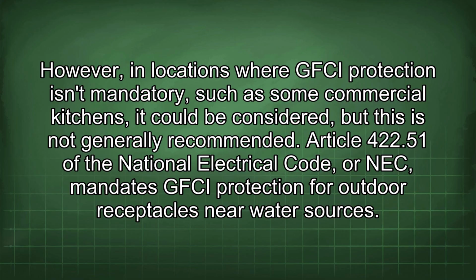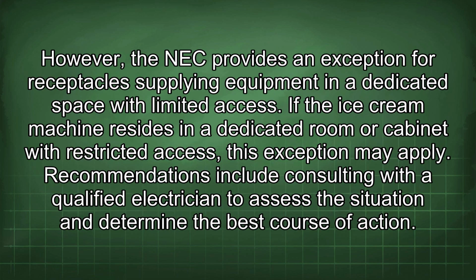Article 422.51 of the National Electrical Code, or NEC, mandates GFCI protection for outdoor receptacles near water sources. However, the NEC provides an exception for receptacles supplying equipment in a dedicated space with limited access. If the ice cream machine resides in a dedicated room or cabinet with restricted access, this exception may apply.